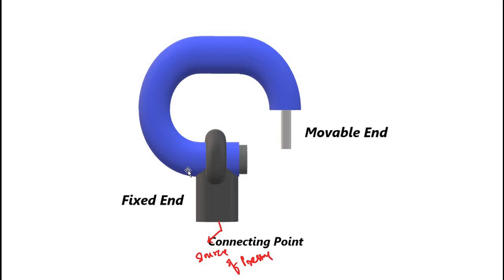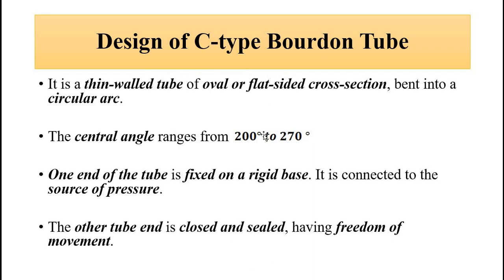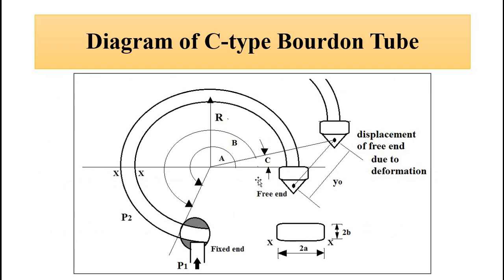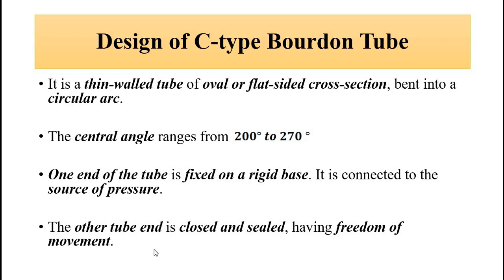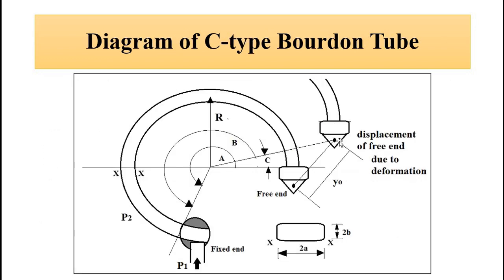Here there are certain things that have to be taken care of. It's a thin walled tube, so that it allows movement and flexibility of the free end, and it is bent into a circular arc, the C-shaped circular arc. The central angle, the angle this makes with the initial position where the Bourdon tube is free and undisturbed, this angle A which the free end makes with the fixed end, ranges from 200 to 270 degrees, which allows total movement of the free end. The other end of the tube is closed and sealed, and that end is free to move.